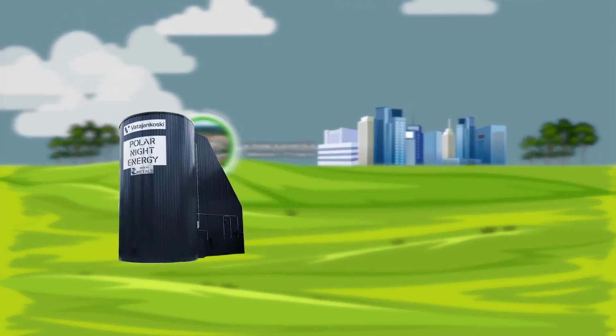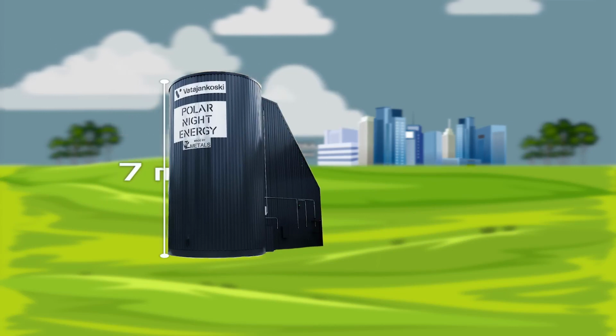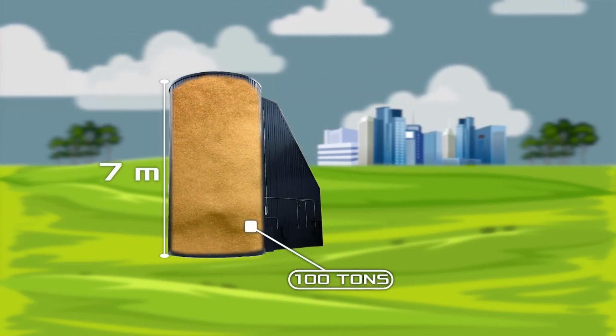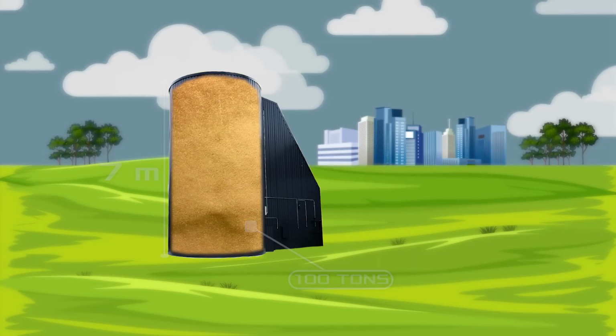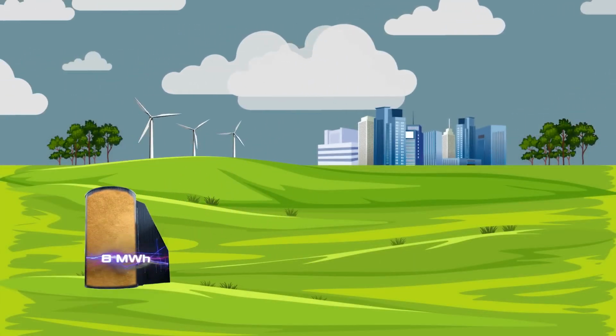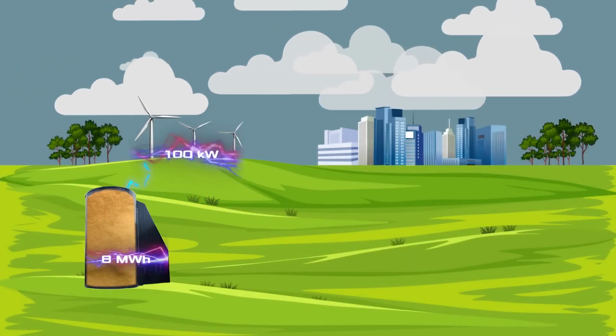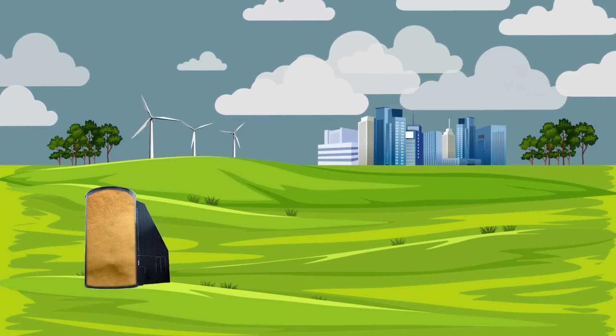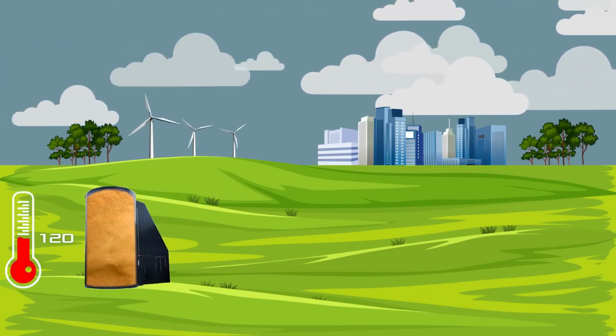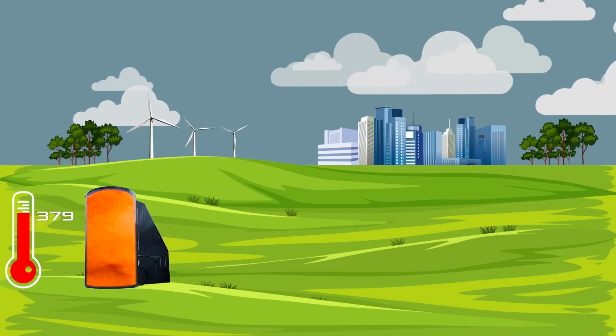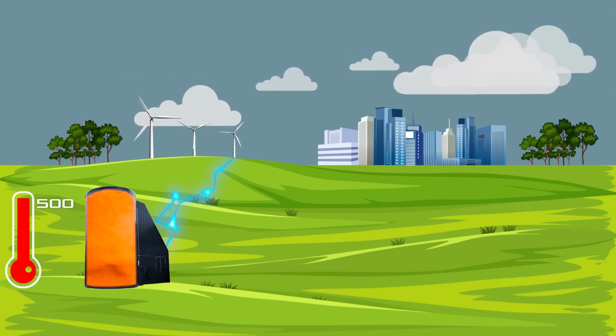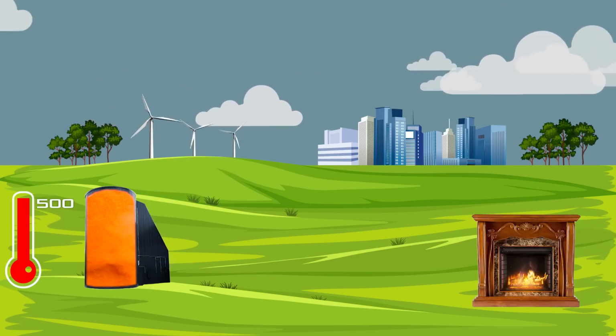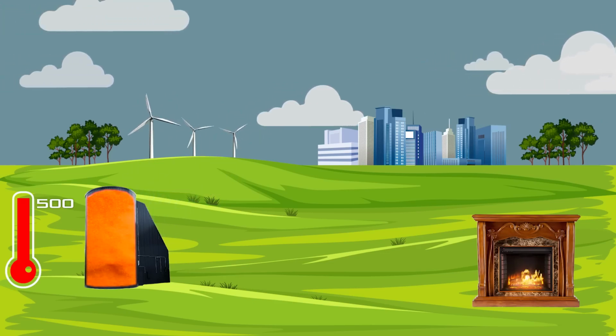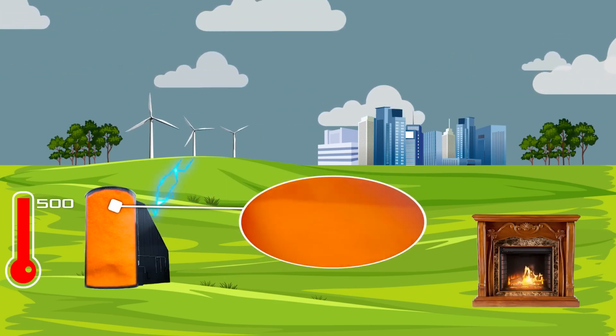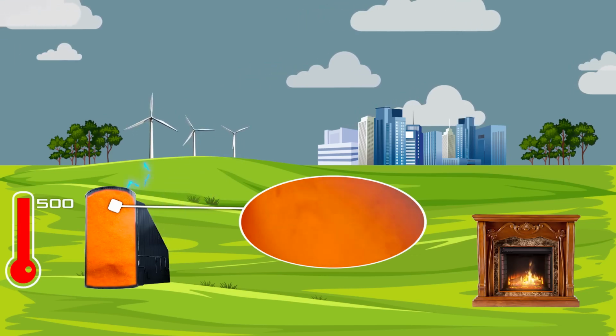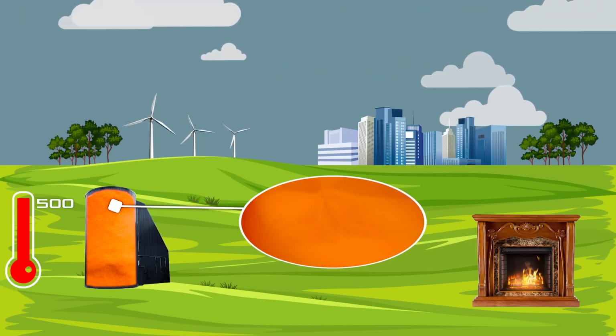This thermal energy storage system looks like a 7-meter-high bunker, inside of which there are about 100 tons of low-grade sand. The device is capable of storing 8 megawatt-hours of energy at a rated power of 100 kilowatts. Cheap electricity heats the sand to a temperature of 500 degrees Celsius due to so-called resistive heating, exactly the same principle by which electric fireplaces work. The sand heats up the air, which circulates inside the battery chamber with the help of a heat exchanger.